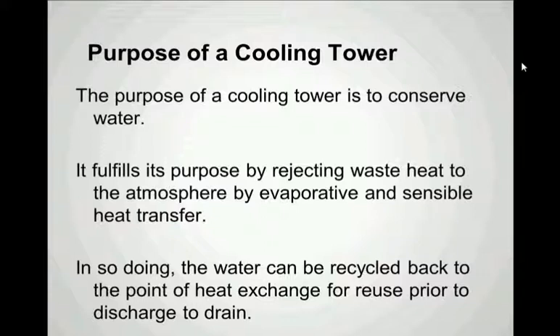This evaporation process at the cooling tower removes heat by both evaporative cooling and by sensible heat transfer, whereby the water is cooled by coming in contact with the colder air. And in so doing, the water that is cooled in the cooling tower can then be recycled back to the point of heat exchange in the cooling water system for recycle and reuse prior to discharge to drain.